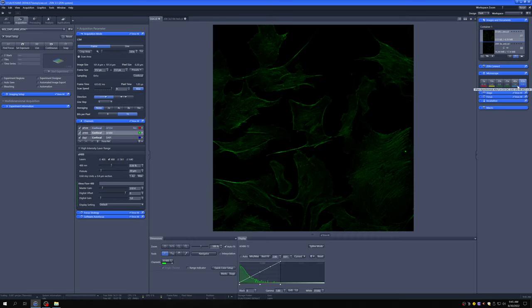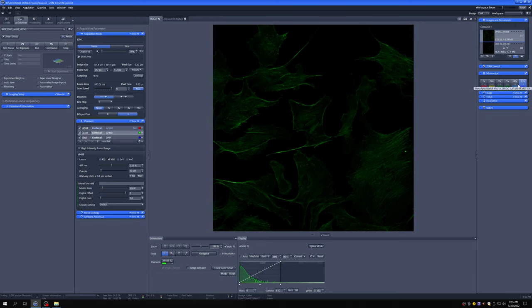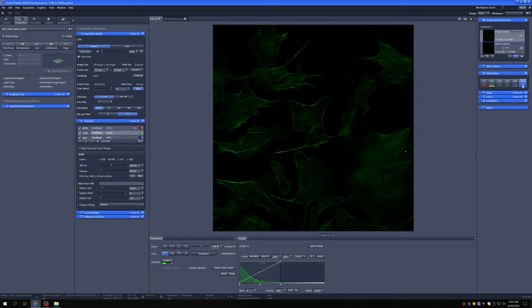It has a shorter working distance, so you can only look about 130 microns into the sample. With the 63x, you can look about 190 microns into the sample. What that ends up meaning is that the 40x is an excellent objective to use if you have cells grown on a coverslip where they're really close to where you're going to image, whereas the 63x is better if you have them, for example, on a slide and then you put a coverslip on top because it's going to be a little bit farther.